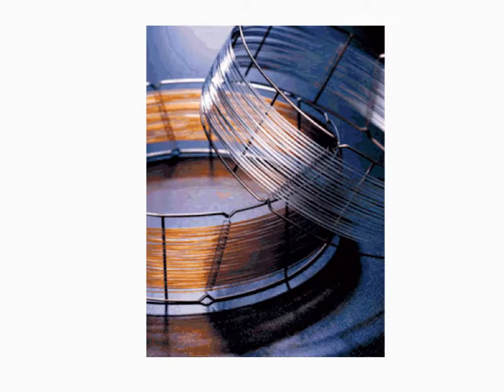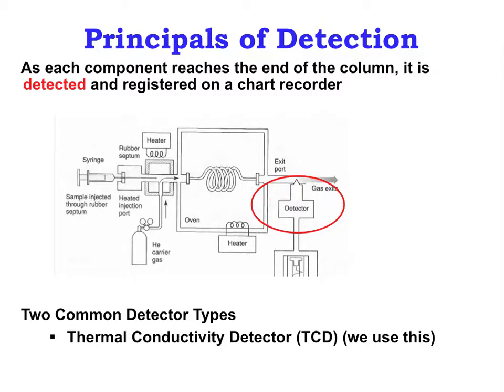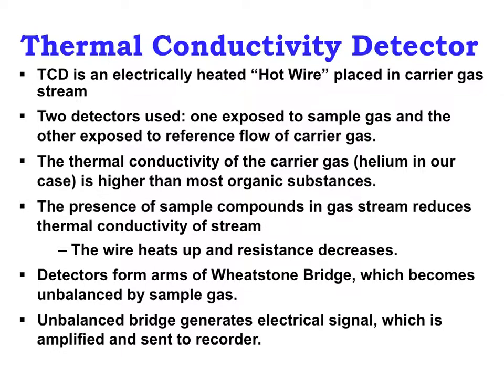Here are some real capillary columns. As the components elute from the column, their presence must be detected in order for us to get any useful information. This is done by the detector, which is located at the end of the column. There are two common detector types. The thermal conductivity detector is the type found on our instruments. We will also talk a little about the flame ionization detector. A TCD uses changes in electrical resistance to detect when a component exits the column. The sample is not destroyed when using a TCD.